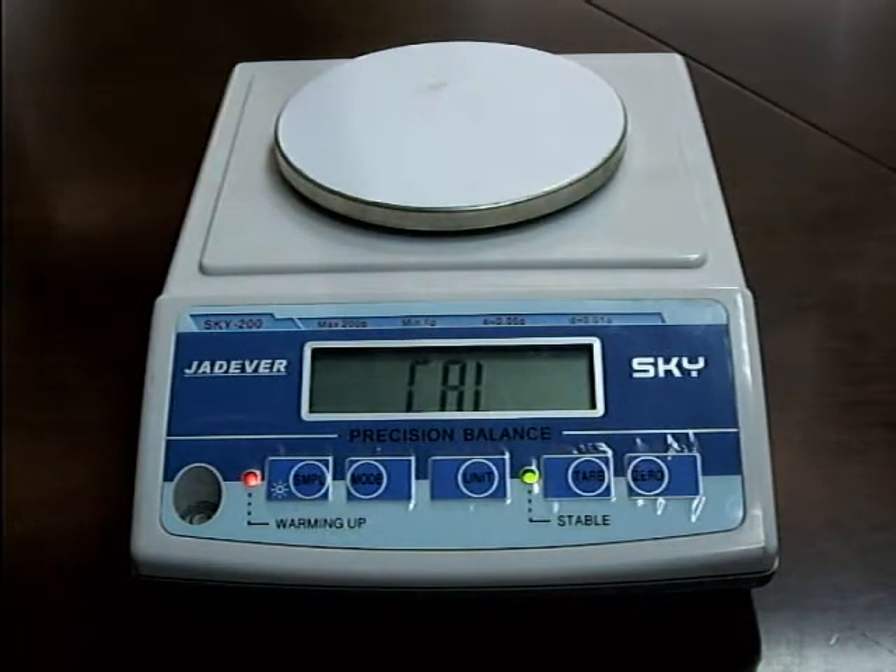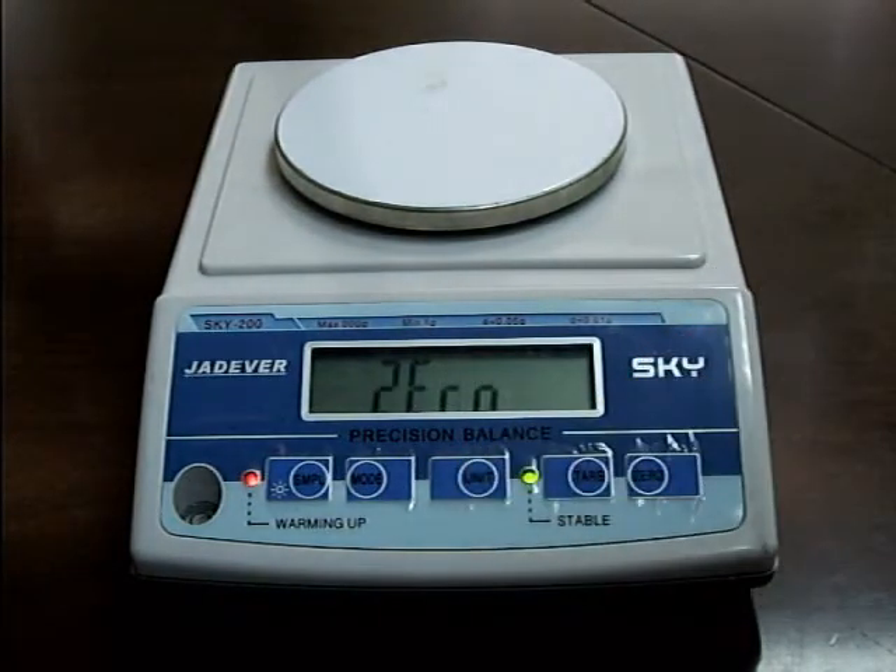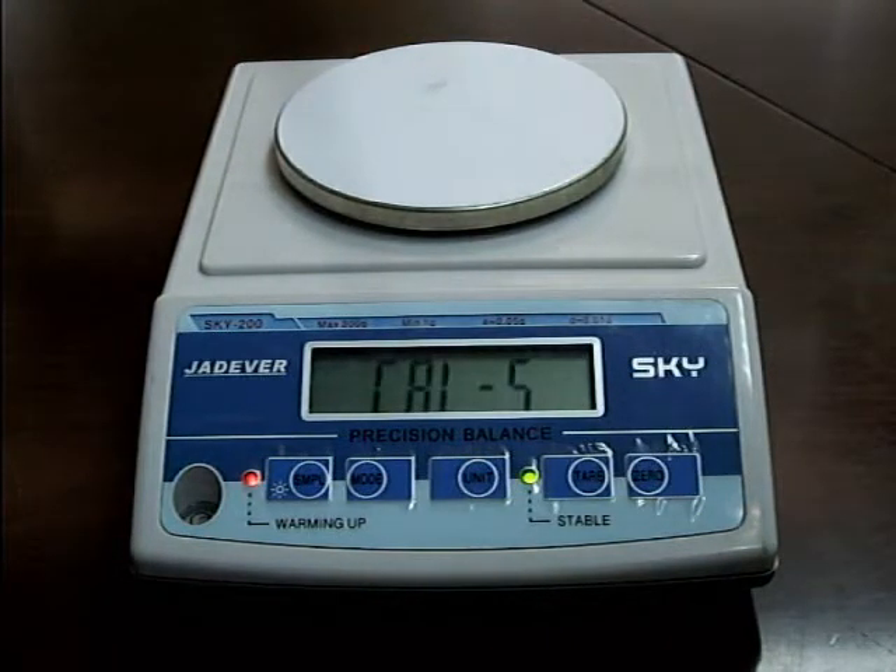Press the unit key. The LCD displays 0, which means zero point calibration. Leave the weighing pan empty. Wait until the LCD displays CAL-5, then put the corresponding weight on the weighing pan.